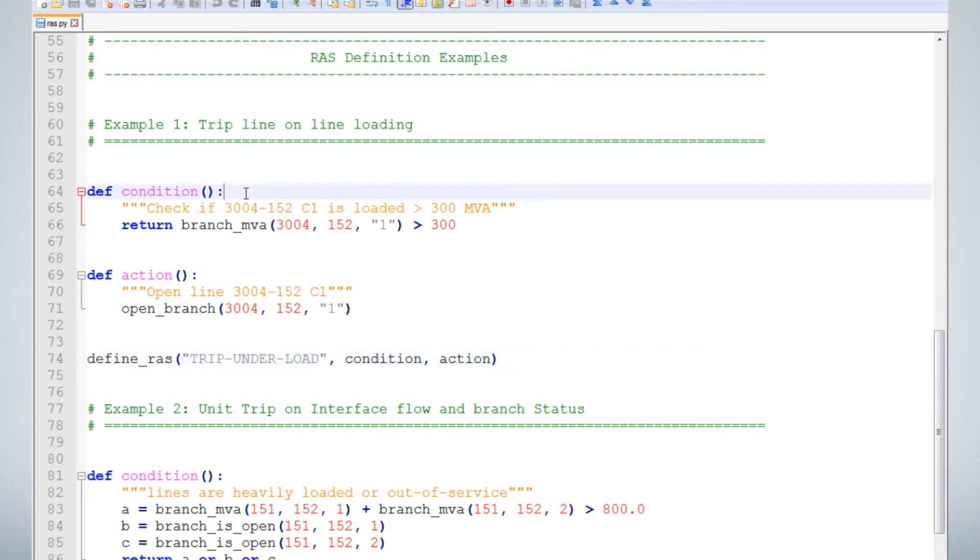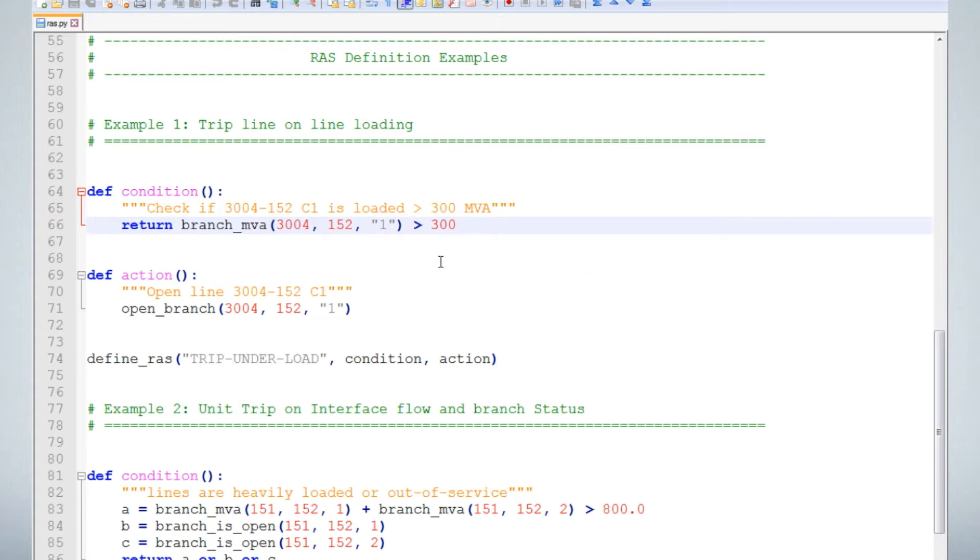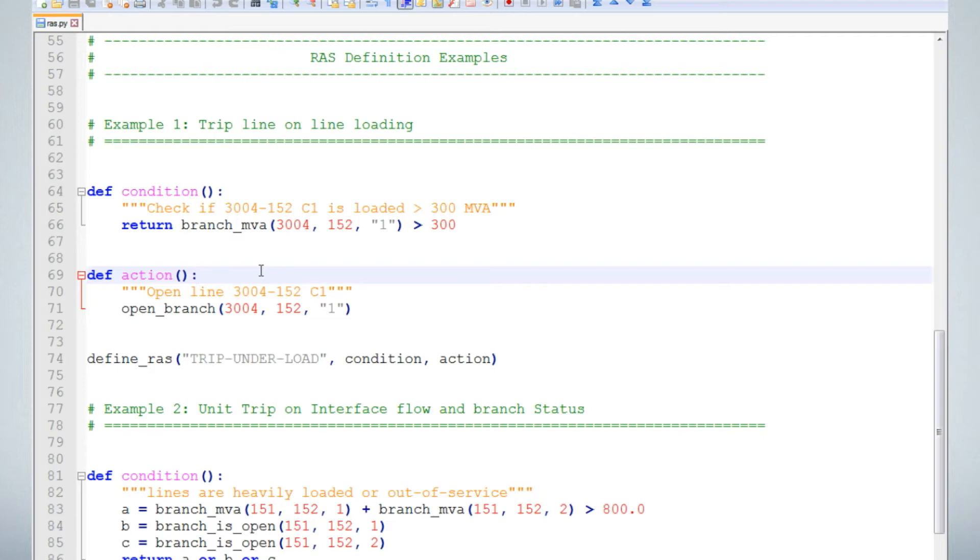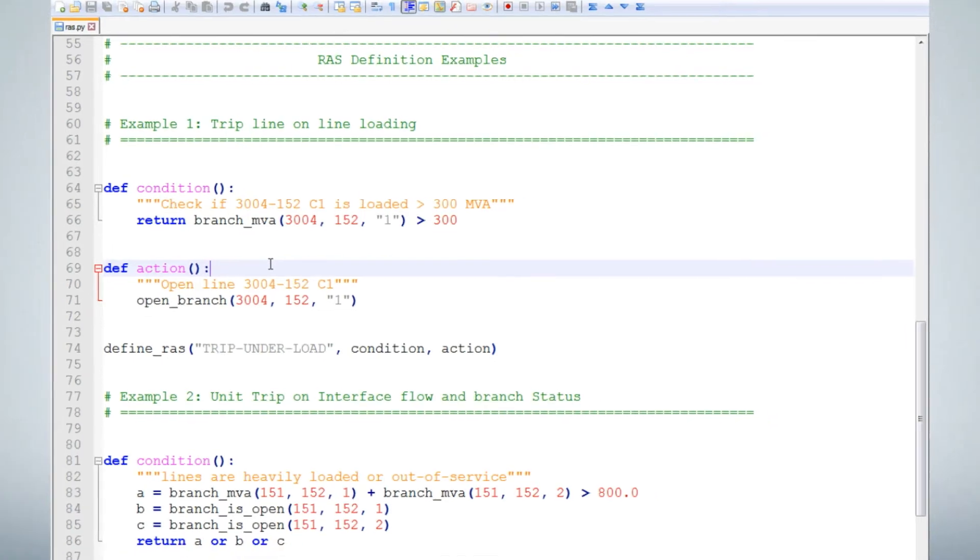A condition function is automatically evaluated by the engine to determine whether the RAS action should be implemented. If it returns true, the RAS is triggered and the action will be implemented. The action function holds all the system adjustments to be implemented for this RAS scheme. The strings at the top and bottom of the function contents are used by the RAS engine as descriptions of the conditions and actions for reporting and logging. We recommend you include these.